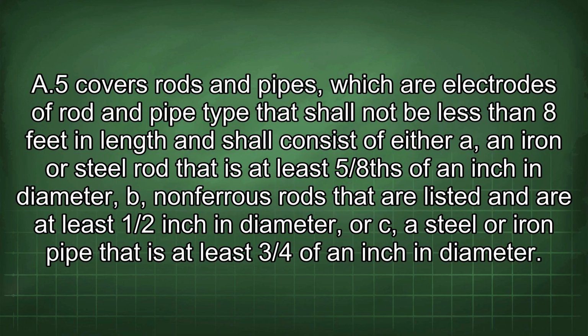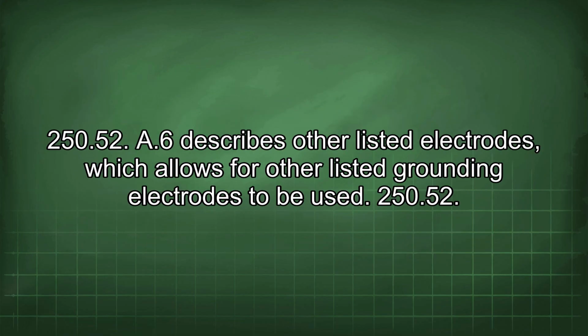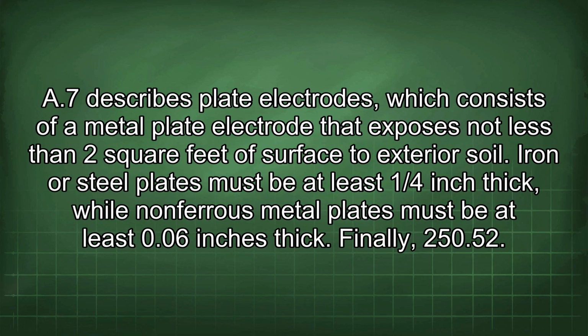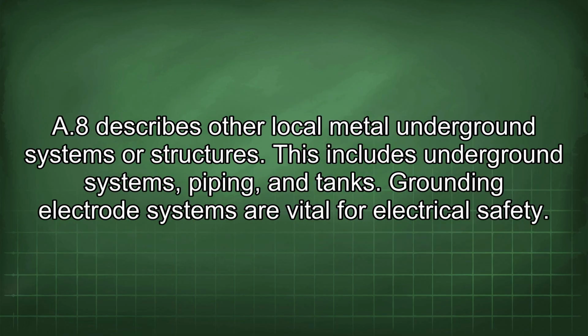250.52(A)(5) covers rods and pipes, which are electrodes of rod and pipe type that shall not be less than 8 feet in length and shall consist of either (a) an iron or steel rod that is at least 5/8 of an inch in diameter, (b) non-ferrous rods that are listed and are at least 1/2 inch in diameter, or (c) a steel or iron pipe that is at least 3/4 of an inch in diameter. 250.52(A)(6) describes other listed electrodes, which allows for other listed grounding electrodes to be used. 250.52(A)(7) describes plate electrodes, which consist of a metal plate that exposes not less than 2 square feet of surface to exterior soil. Iron or steel plates must be at least 1/4 inch thick, while non-ferrous metal plates must be at least 0.06 inches thick. Finally, 250.52(A)(8) describes other local metal underground systems or structures. This includes underground systems, piping, and tanks.